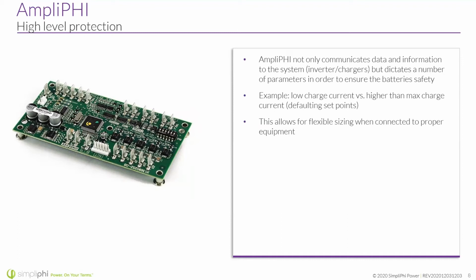If we look deeper, we have these high level protections built in where it will say, hey, your inverter is too large for my battery bank, so I'll throttle down the output and make sure it never discharges too much. This is something most inverter companies are implementing within their set points, but the battery management system can really take advantage of that, and we can rely on the BMS to allow for flexible sizing.